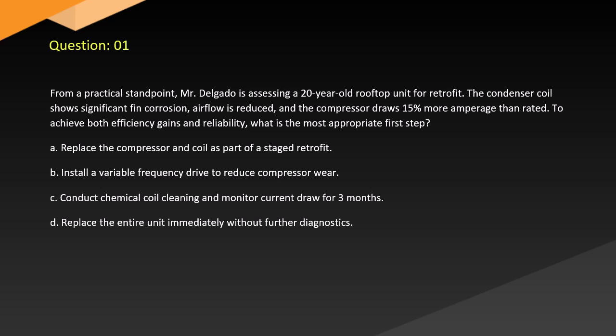A. Replace the compressor and coil as part of a staged retrofit. B. Install a variable frequency drive to reduce compressor wear. C. Conduct chemical coil cleaning and monitor current draw for 3 months. D. Replace the entire unit immediately without further diagnostics.